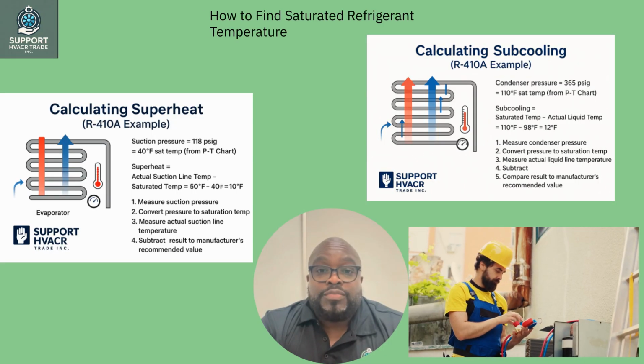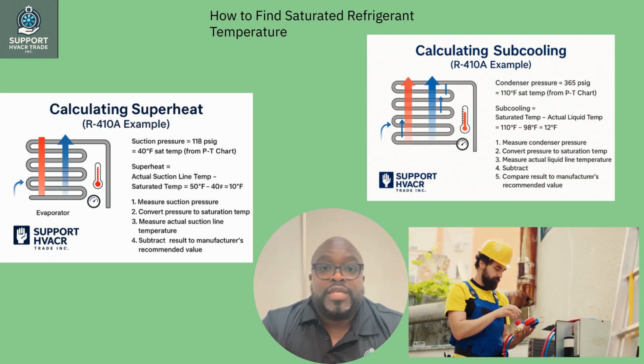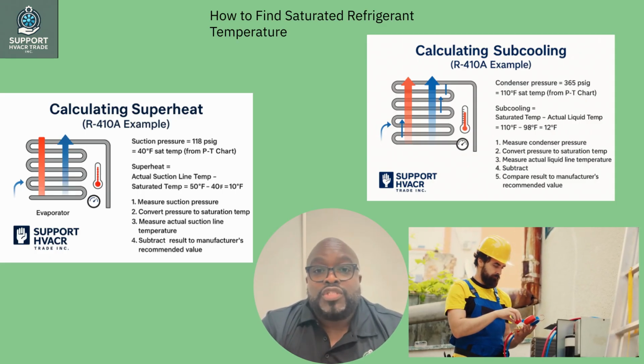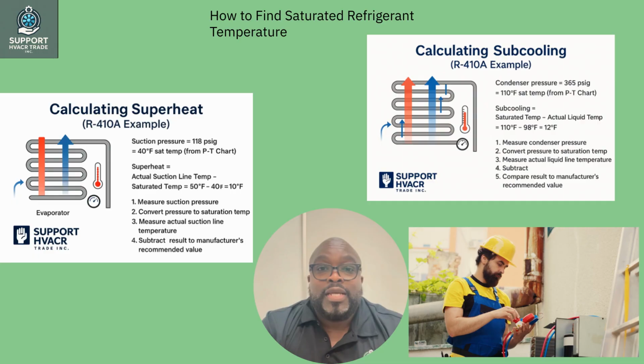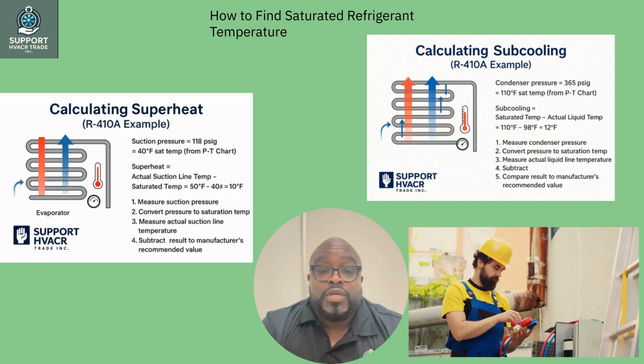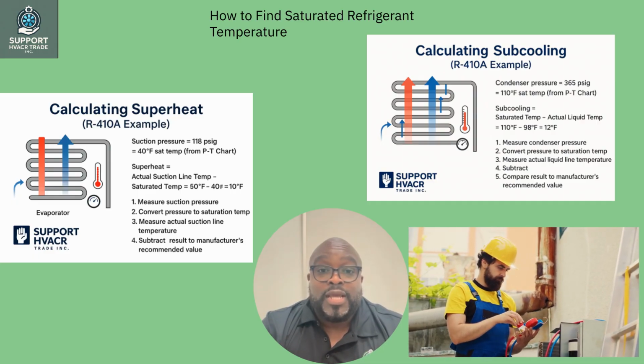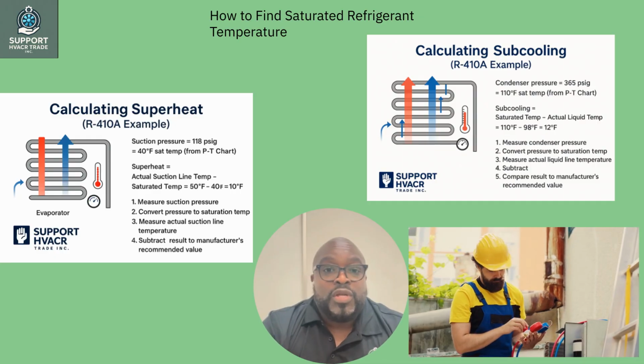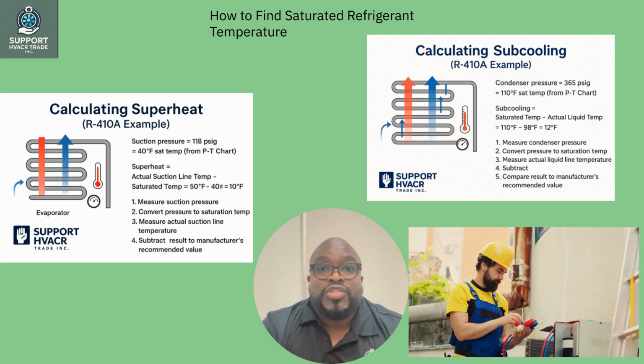Understand what saturated means. A refrigerant is saturated when it is at the point of changing state, either boiling, evaporating in the evaporator, or condensing in the condenser. At this point, pressure and temperature are directly related. That's why we use a PT chart.